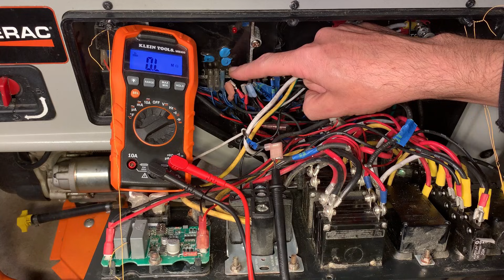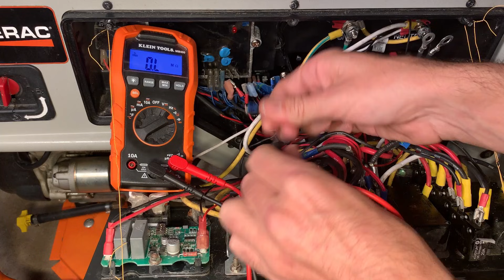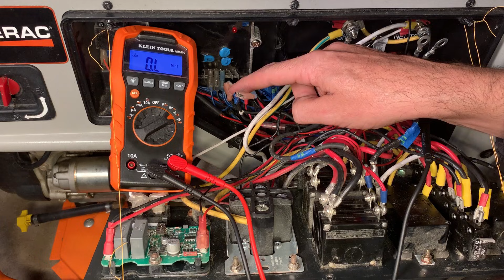Now, if I check this other winding here, which apparently is the sense, and connect it over to the DPE - it was in the DPE spot on the fuse - we get a number very close to the main winding, which is what I'd expect to see on the sense winding. So I need to get this off, relocate it to where it should be, and flip-flop some wires, and this thing might work.